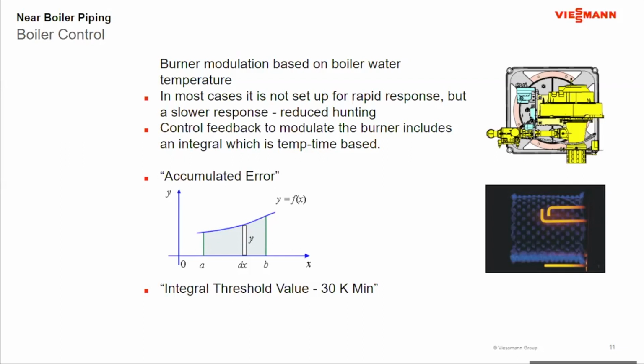So we don't have to have a boiler control that's set up for rapid response. We actually want it for a slower response. The plus side of that is it reduces the amount of hunting that happens. It hunts less, and the burner can run for a long period of time without making adjustments. So we're really looking for a slower response.